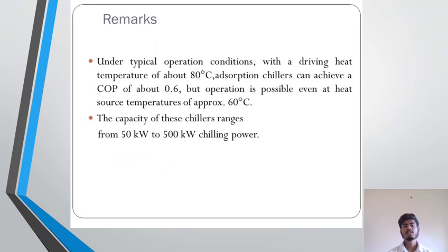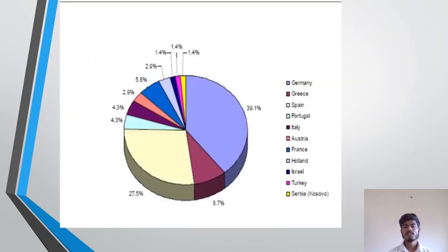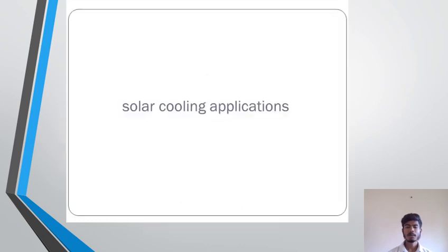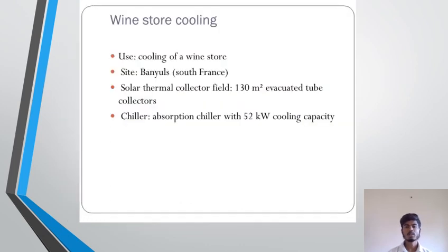The remark for this one is that under typical operating conditions with a driving heat temperature of about 80 degrees Celsius, adsorption chillers can achieve a COP of about 0.6, but operation is possible even at heat source temperatures of approximately 60 degrees Celsius. The capacity of these chillers ranges from 50 kilowatt to 500 kilowatt chilling power. And here we can see the chillers in different countries like Germany, Greece, Spain, Portugal, Italy, Austria, France, Holland, Israel, Turkey, and Serbia.